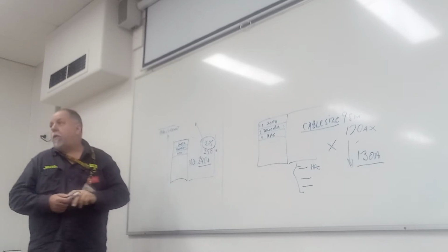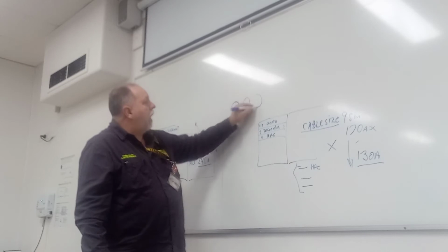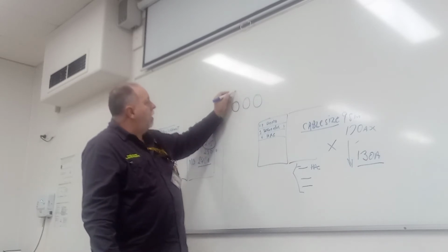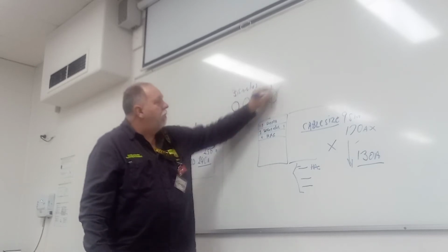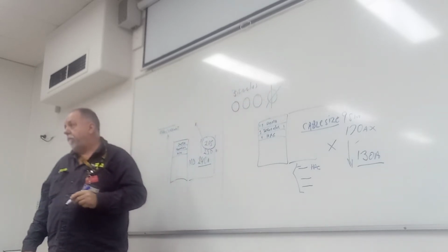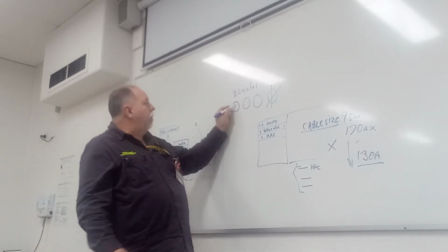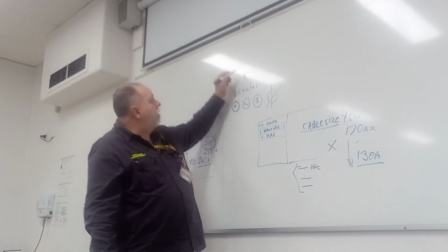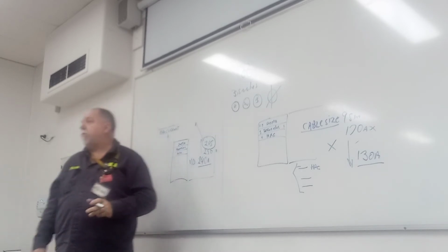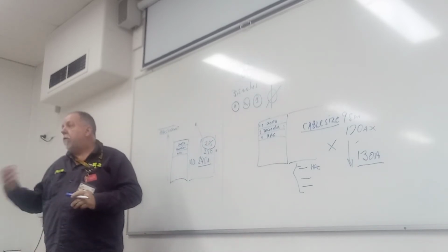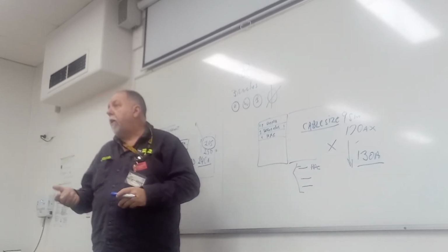When we look at cables in the AS 3008, you have three-phase cable, which will be either three singles, right? Don't worry about the neutral. The neutral doesn't carry full current. Only the three actives, red, white, blue. They'll either be three singles or a multi-core with three, it's three core. Some questions say 4-core or 4-core with earth, and people are looking for 4-core in the book. They don't talk about it.